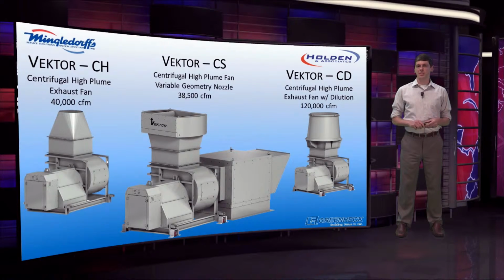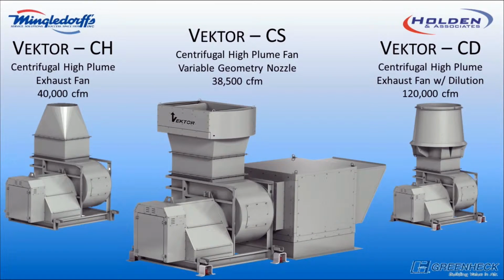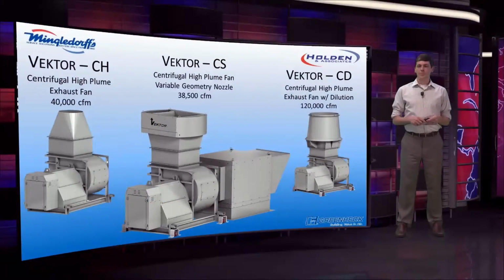Now we'll talk about the Vektor C series of fans. The C series utilizes a centrifugal wheel, which can generate higher statics. This is great for heavy filtration applications and can handle statics up to 14 inches. The C series has the same options of the CH, a CD, and a CS. The CD in this case, centrifugal wheel with dilution, can go up to 120,000 CFM.